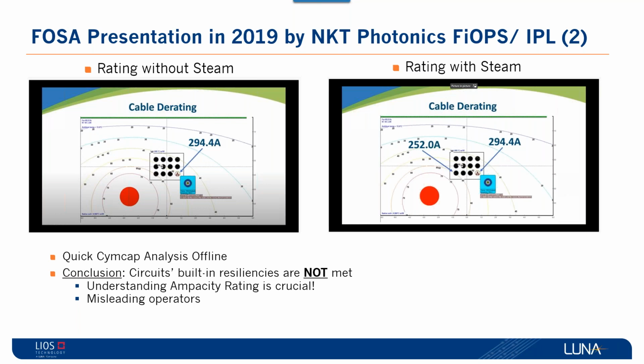What was very important about that case study was the fact that it was asset monitoring. The asset monitoring was to focus on catching when the steam line is affecting the duct bank and the power cables, and reducing the lifetime of the power cable, because the duct bank gets destroyed by the high temperature. By losing the power cables, the circuits, they have to reinstall the circuit. It takes a long time.